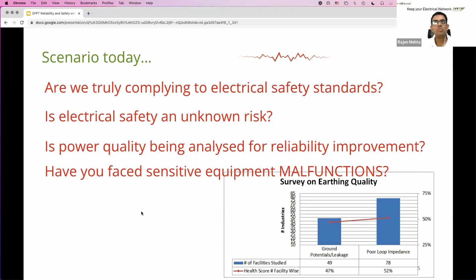We found that in 49 facilities, 47% had high incidences of ground potentials or leakage currents in the earthing network. And 70 out of 78 facilities, 52%, had very high earth loop impedance, meaning the earthing wasn't doing the job it was supposed to. Plant maintenance or facility management personnel typically focus on earth pit management rather than earth loop impedance near the equipment, which is what really shows whether equipment earthing is healthy and whether protective devices will operate if a fault occurs. This is again a telling statistic, not a small number.